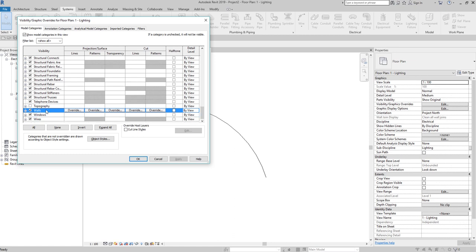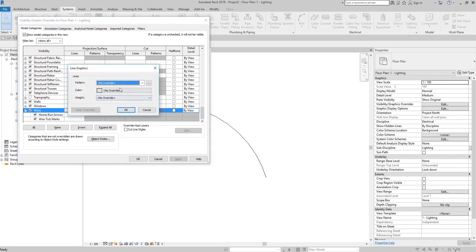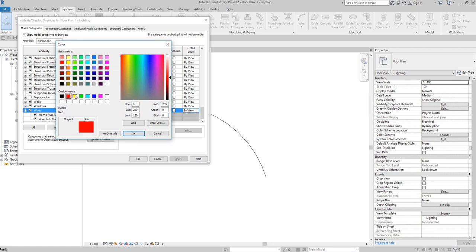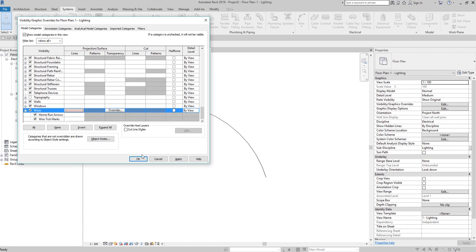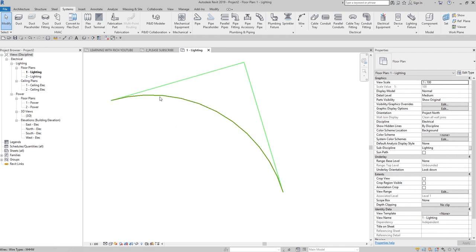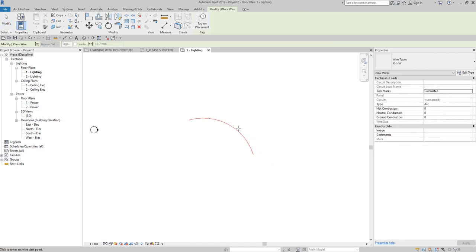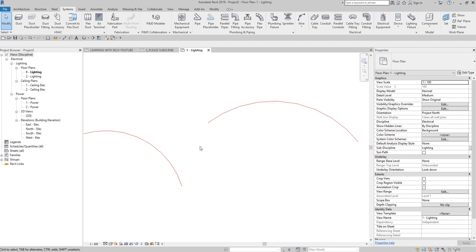You can type VV to open Visibility/Graphic Overrides, then look for Wires and click on it. You can change the override here — I'll change the color to red and select OK. That's what will happen: it changes the wire color to red. Every wire you create will now display in red based on the Visibility/Graphic Overrides.